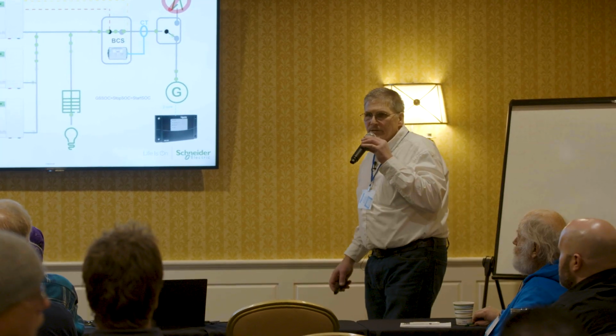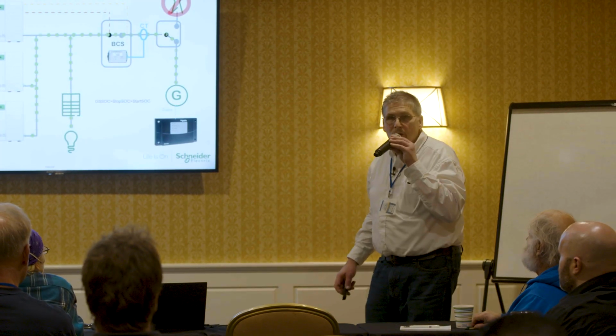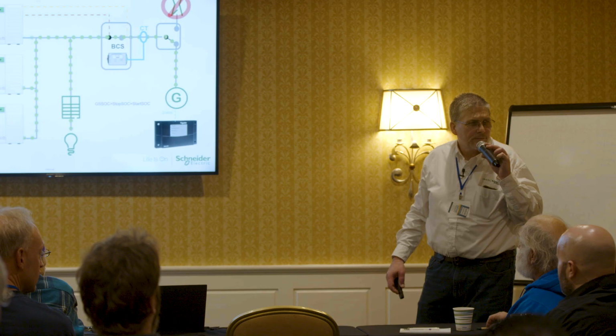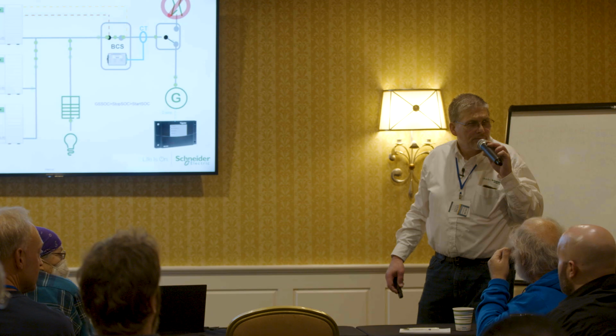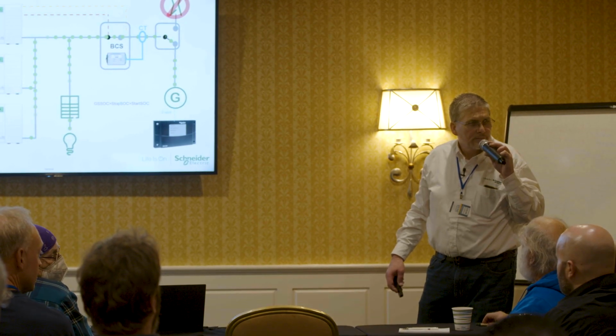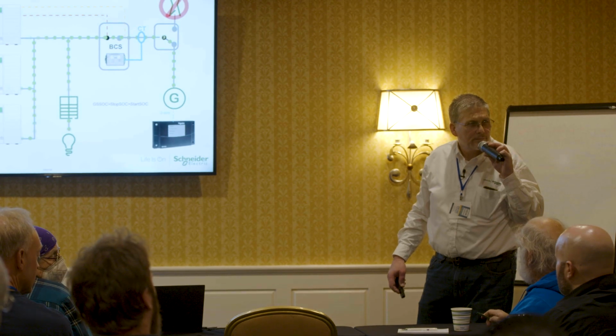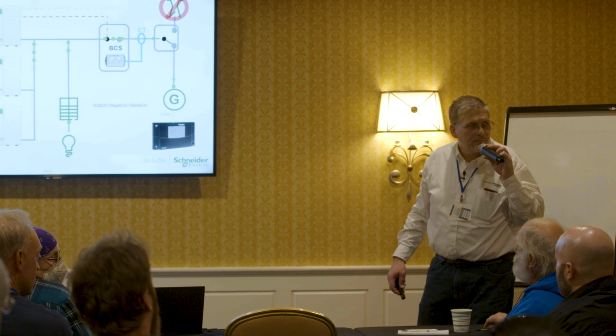Yeah. In that case, I would use the quiet time to make sure that we're not allowing the generator to start during solar hours. But I would be careful with that setting, Eric, because in the event that the batteries are low, that's going to override your quiet time. Essentially, generators are expensive, and anytime you connect them to a system, in my case off-grid, you're out of luck. So a contactor to me seems to be a very inexpensive way.